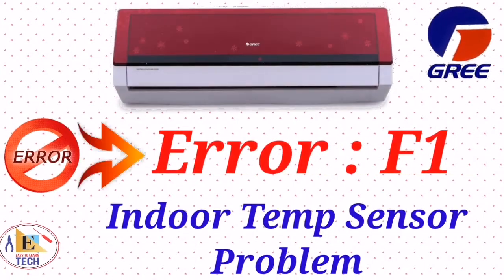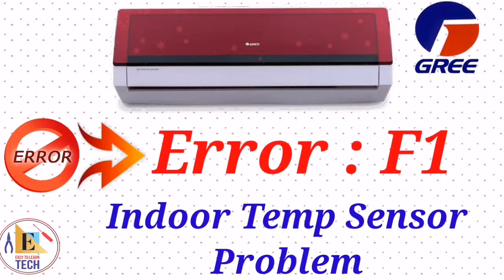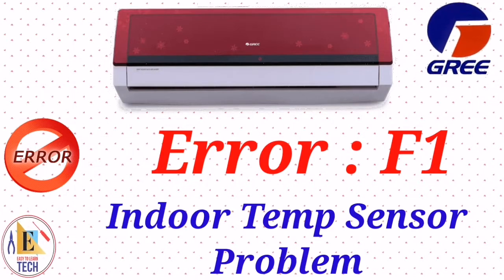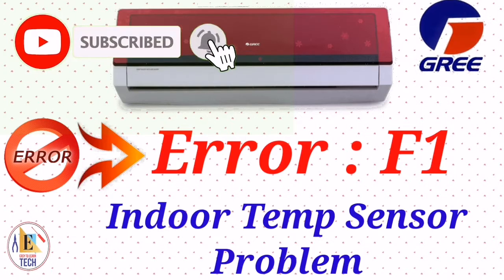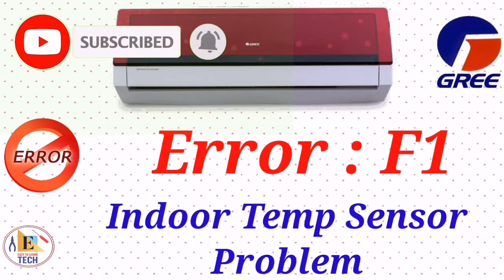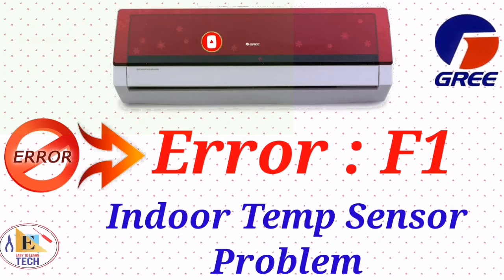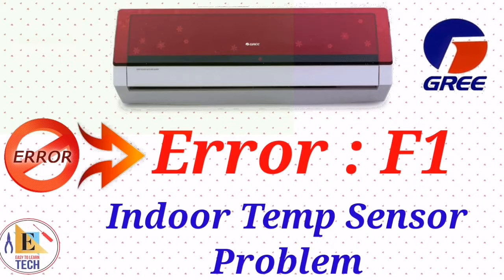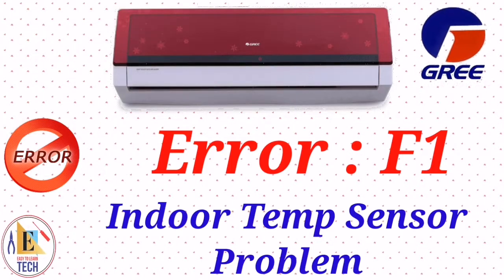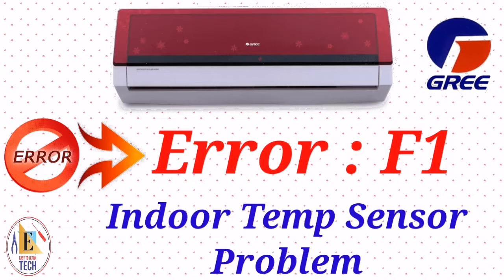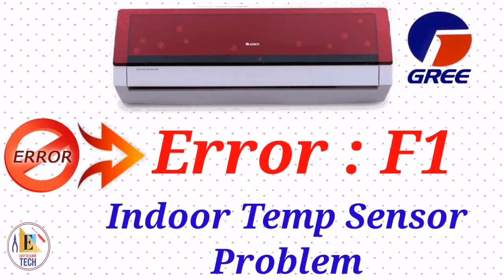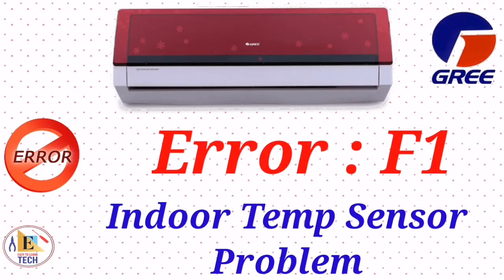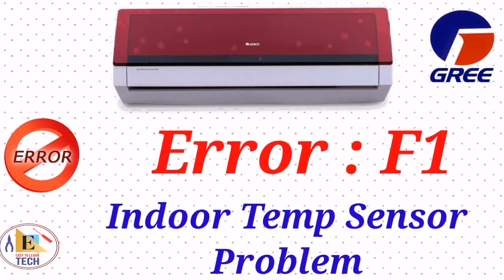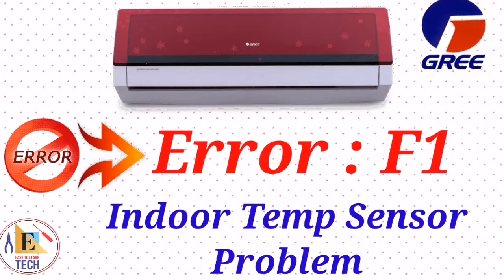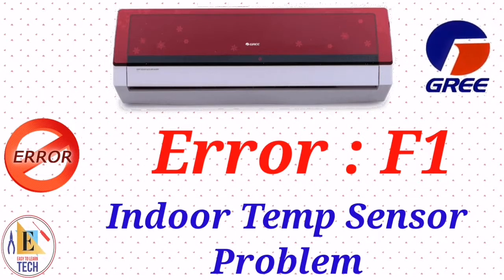When you see F1 in your display, it means indoor temperature sensor problem. The indoor temperature sensor is installed just above the evaporator coil. We can remove the filter and you can see the indoor temperature sensor. First of all, you have to check the placement, if the placement is good or not. Then you have to check the connection in your PCB, if it is properly connected or not. If it is properly connected, then you have to check the resistance of the indoor temperature sensor. And if the resistance is not okay, then you have to change the indoor temperature sensor.